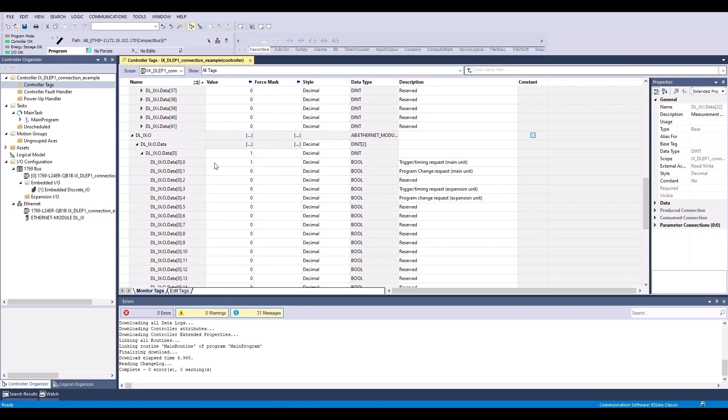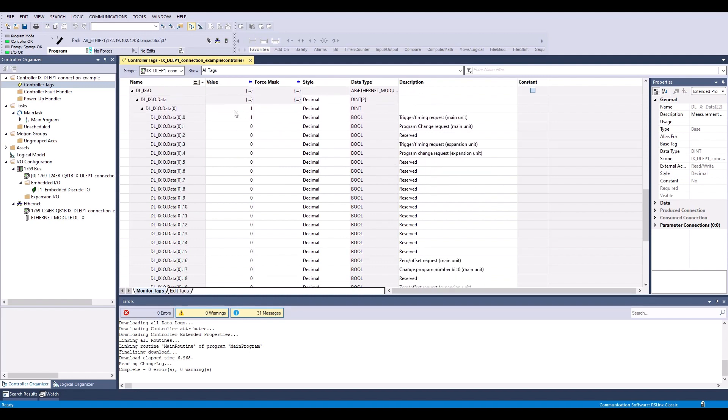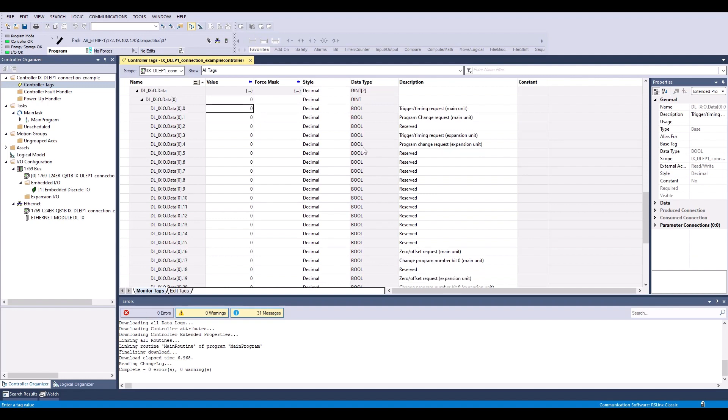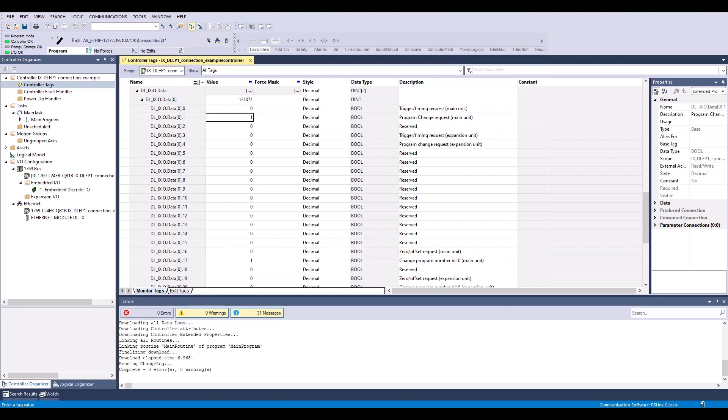Next I will show you an example of how to change programs. So the first thing I'm going to do is take that back to a 0. And let's say I want to go to program 1 for example. I'm going to set this change program number bit 0 to a 1, because my program changing is binary. And then I'm simply going to send this program change request for the main unit. And you'll see that I've now changed to program 01, which is empty not programmed.